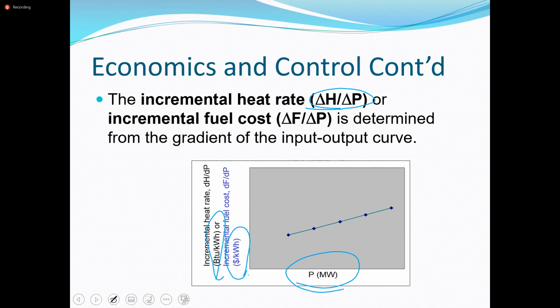Yes? So the cost of producing an additional unit will increase. And it will continue to increase until I then get it equal to the next most efficient, and then we start taking from both. But the key point that I want you to focus on here is that as the output increases, so does the incremental fuel cost. All right, that's the key point from this graph.